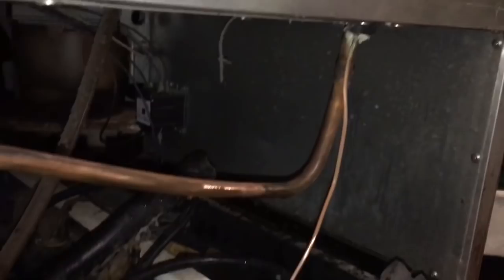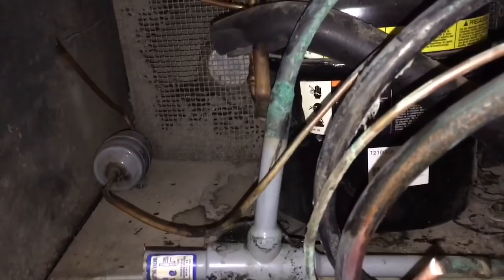Alright, so got this thing cut loose, sanded the pipes for them, cutting it loose. I think I'm going to throw a new cap tube in here, freezer. This is past repairs. Yeah. New suction pressure regulator going in. Okay, just cut loose and the electrical box is out of the way now, so it can come out of here. Oh, ready to yank the condensing unit out.